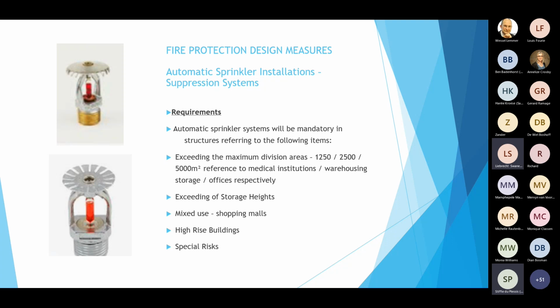With different sprinkler heads you can achieve different protection measures. Sprinkler systems are something we could debate all day, because any sprinkler design is based on the category of product being stored - for example a category 4, which means high hazard, flammable liquids, and special risk requirements.